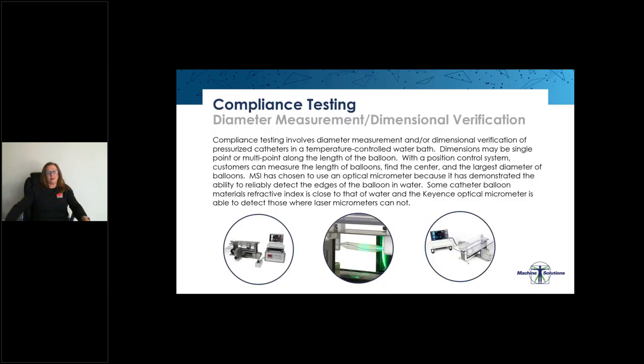Compliance testing involves diameter measurement or dimensional verification of pressurized catheters in a temperature-controlled water bath. Measurements may be single point or multi-point along the length of the balloon. With the position control system, customers can measure the length of the balloon, find the center of the balloon, and the largest diameter of the balloons. It can also be used to take proximal, medial, and distal measurements of the balloon.